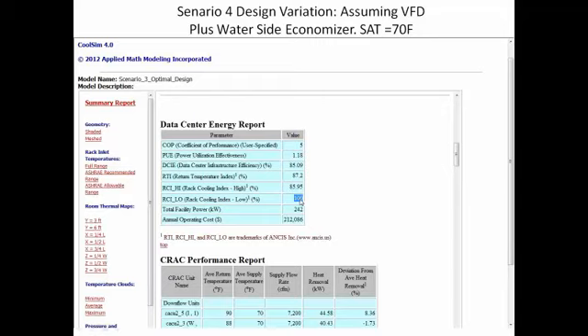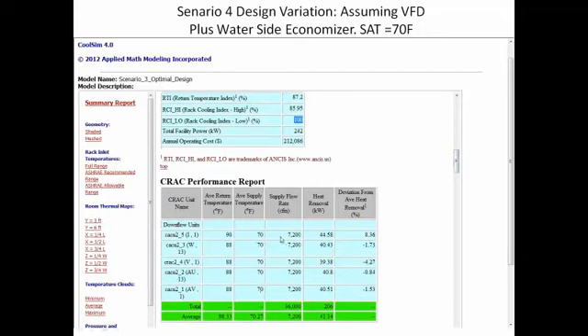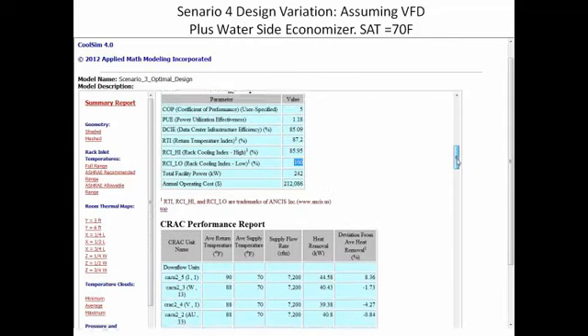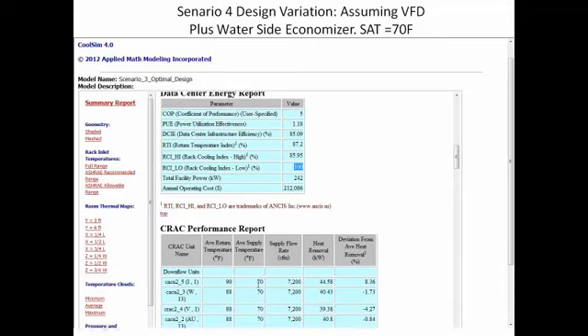Remember, that's a cubic relationship. So as I reduce the fan speed, I save energy at a ratio of greater than a square. Theoretically, it's cubed of the RPM. And also here, because I'm running at a higher supply temp, you see I've moved the supply temps up to 70. The efficiency of the mechanical system goes up. And that ratio is, you're getting about 3.5% for every 1.8 degree F that you move. So you're getting a couple percent per degree every time you move it. So 10 degrees is worth about 20% of mechanical energy alone, not to mention the economizer window opening up quite broadly. So we're headed in the right direction here.